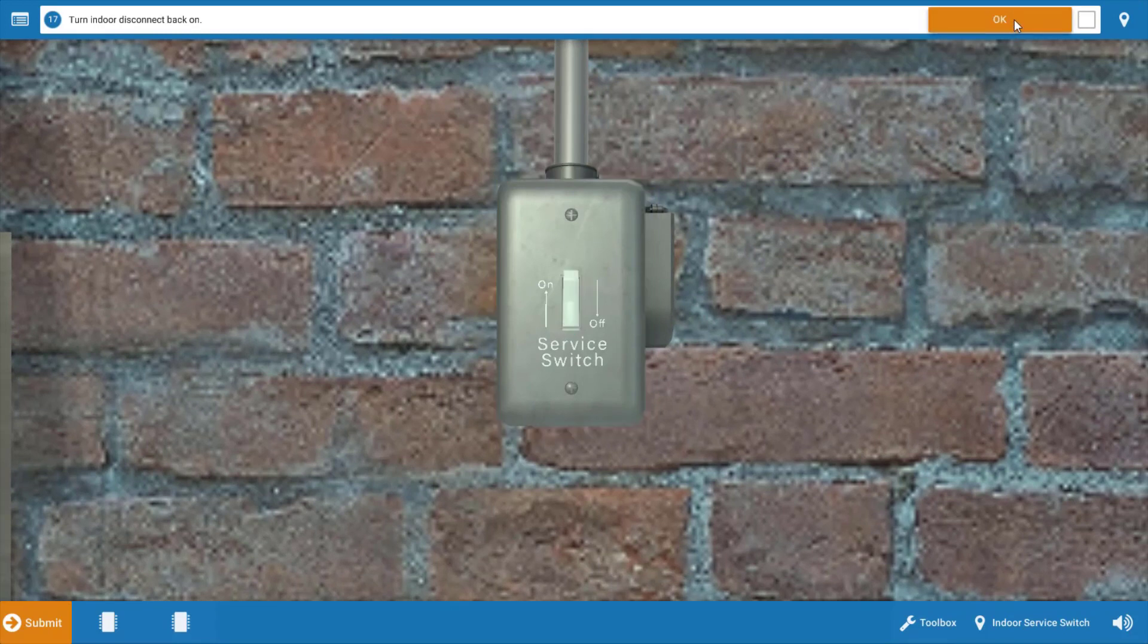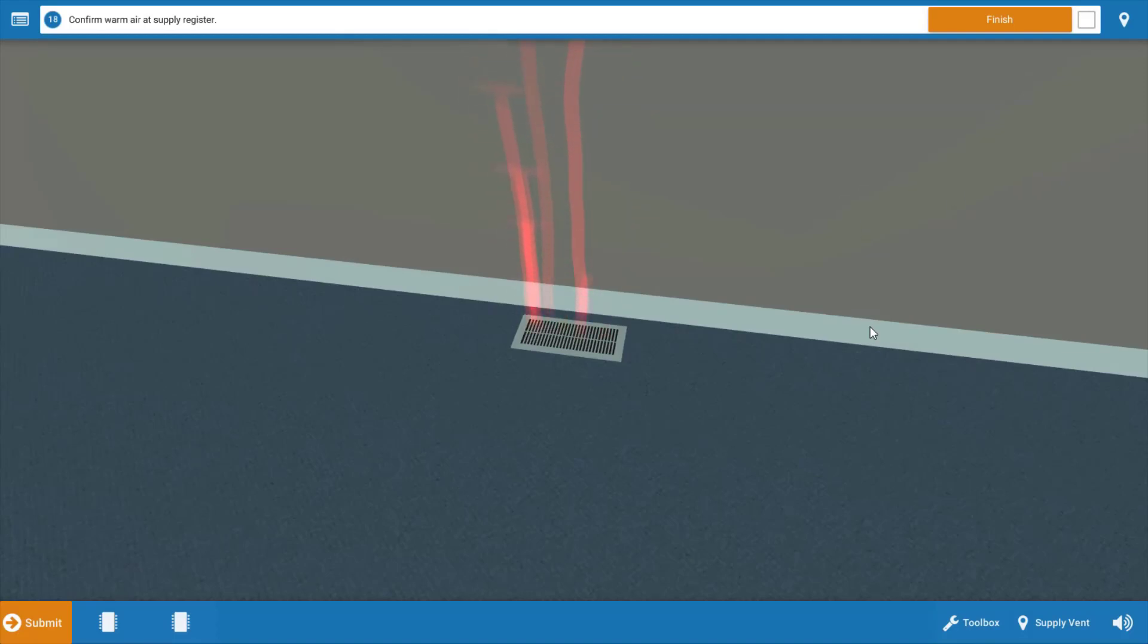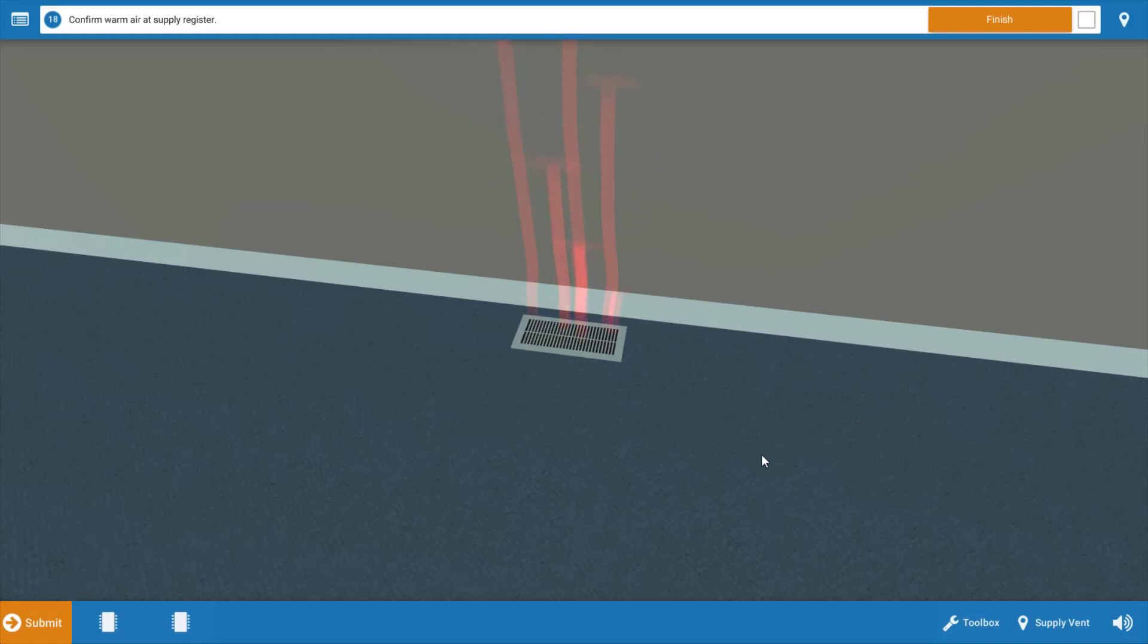Once we've turned the power back on, we're going to click OK on the procedure guide and observe one full cycle of operation to make sure all loads are operating properly. You may want to pull the indoor filter to make sure it's clean and replace it if necessary. Last but not least, we're going to go up to the residence and ensure that heat is being received through the floor registers. As we can see from the red graphic here, we do in fact have warm air entering the space.